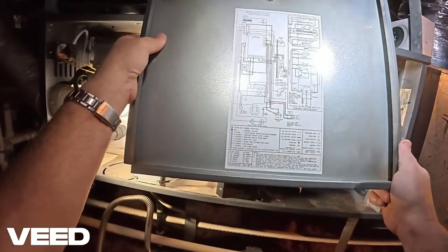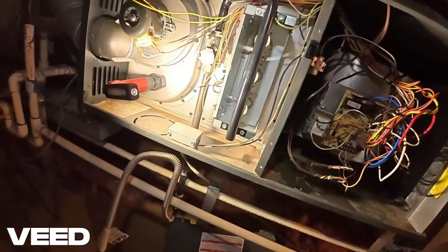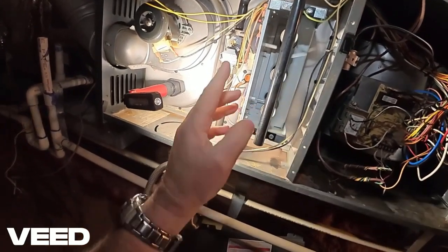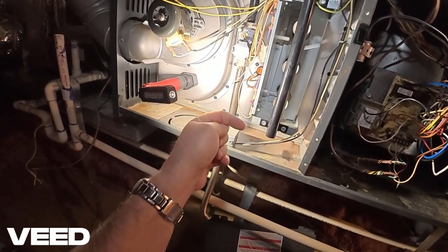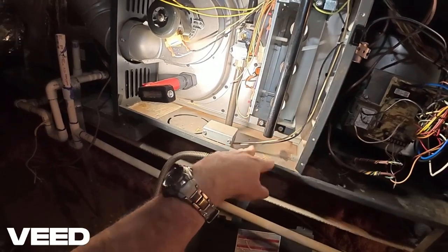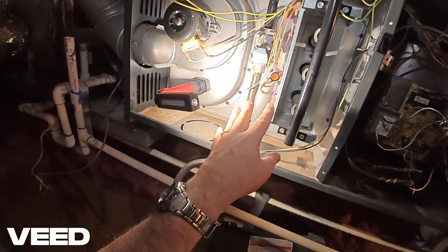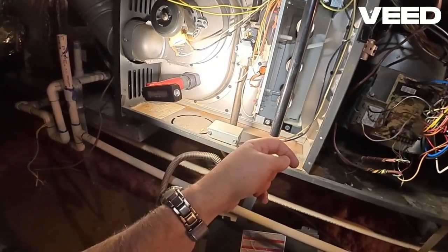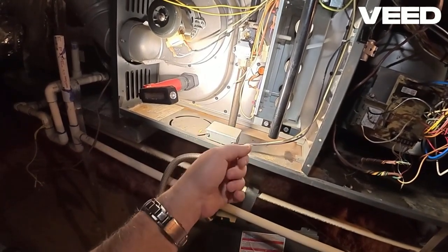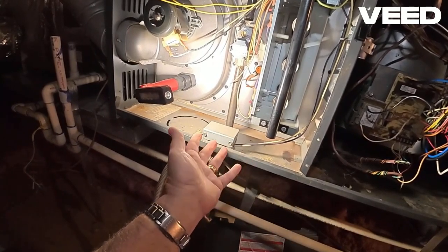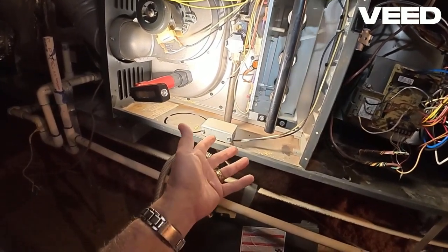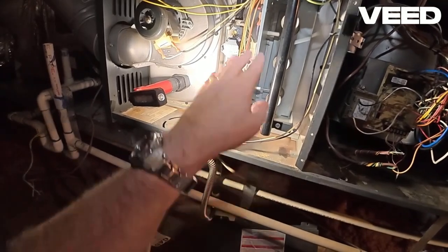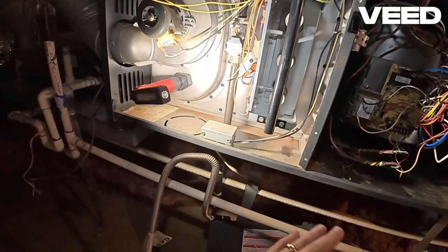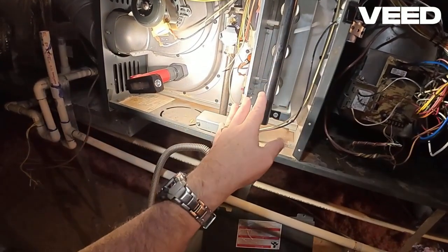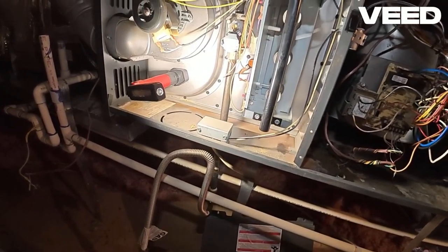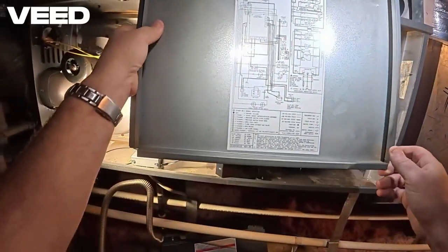Next, we look at flame sense without gas valve. So this one down here is our flame sensor, and its job is to sense the flame once the gas has ignited and is on. It'll sense flame and do a job called flame rectification and send a signal back to the control board that we have flame. And then that'll initiate about a 30 or 45 second delay and turn on our blower motor. So if that is sensing flame and the gas valve is not on, that often points to an issue with the control board. It could be with that sensor itself, but it's more likely a control board issue. And we'll talk about that one more here in a moment as well.